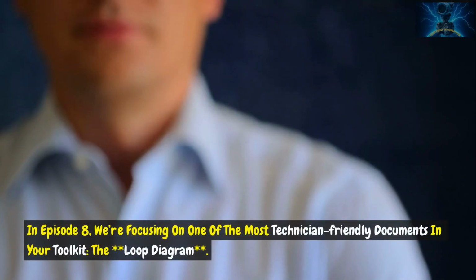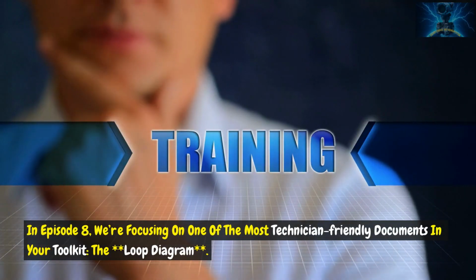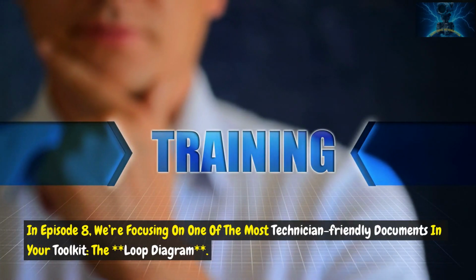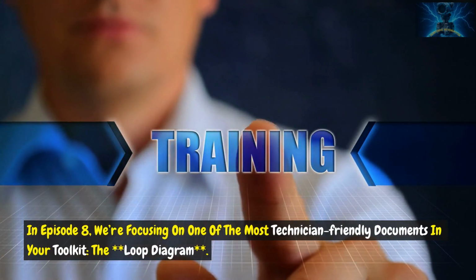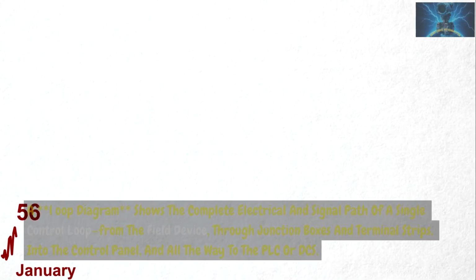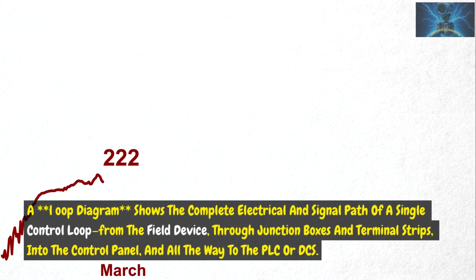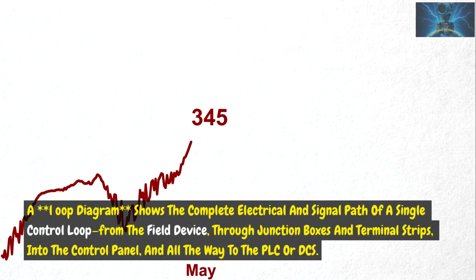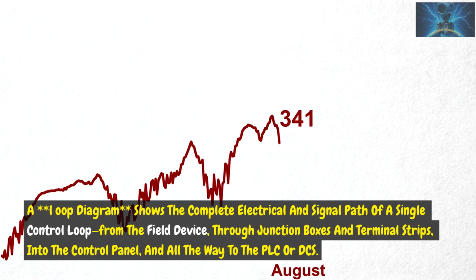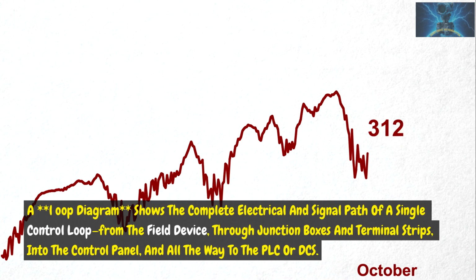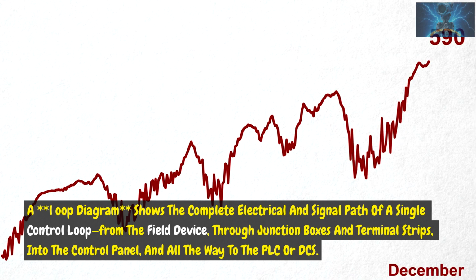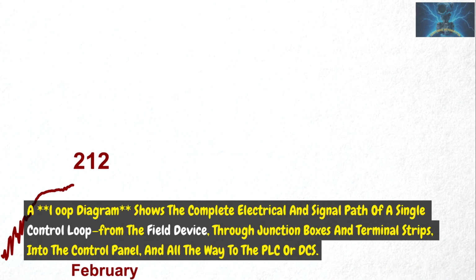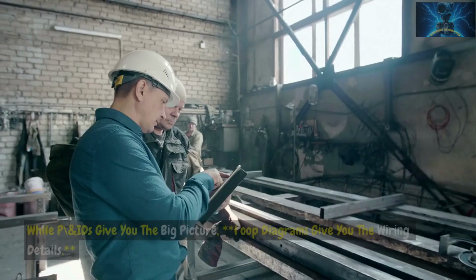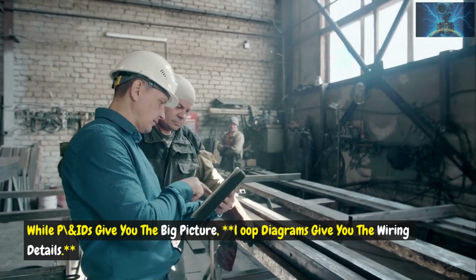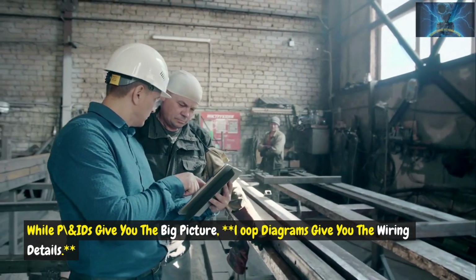In Episode 8, we're focusing on one of the most technician-friendly documents in your toolkit, the loop diagram. What is a loop diagram? A loop diagram shows the complete electrical and signal path of a single control loop, from the field device, through junction boxes and terminal strips, into the control panel, and all the way to the PLC or DCS. While P&IDs give you the big picture, loop diagrams give you the wiring details.